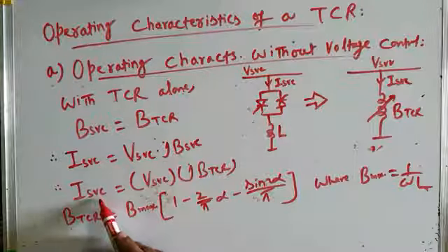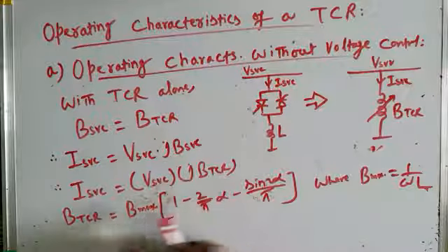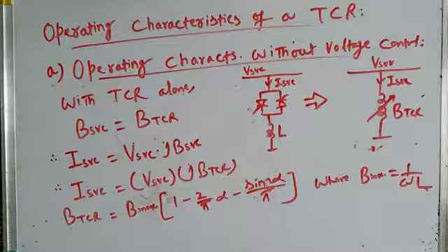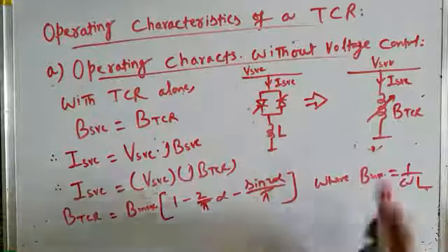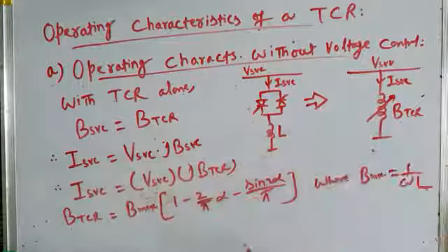That will give us, for a given delay angle or firing angle, how much current is flowing through this TCR, ISVC. And knowing ISVC, we will be able to find how much reactive power is being absorbed by TCR.